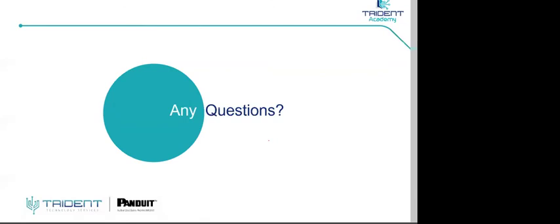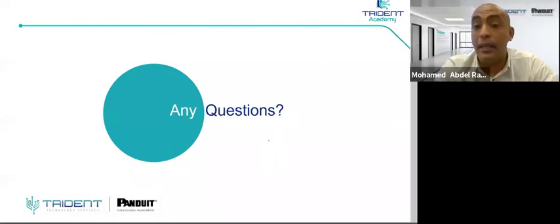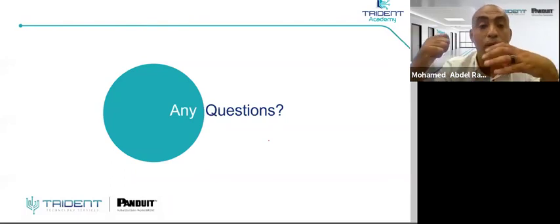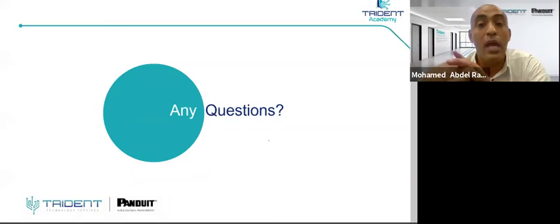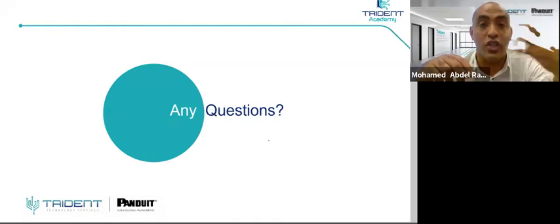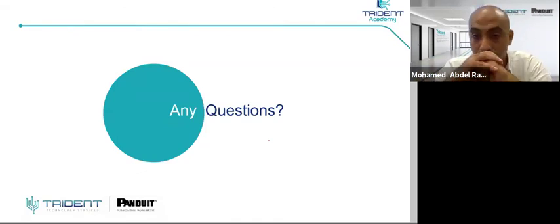A second question, is Panduit's Pan-MPO connector compliant with industry standards? Yes, sure. The Pan-MPO connector meets all industry interface standards. It is completely intermatable with other MPO connectors. You can connect it with other MPO. The only advantage, as we said, is that this is the only connector that can change the gender. You can change the polarity in the field.